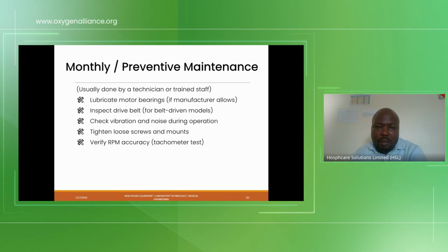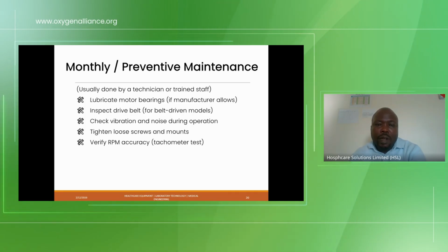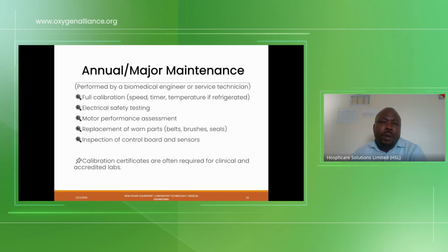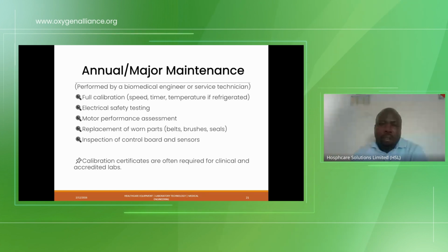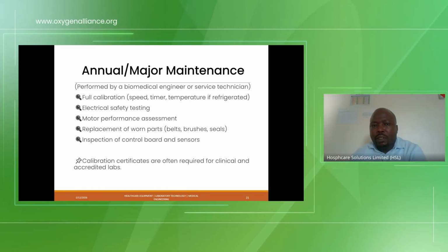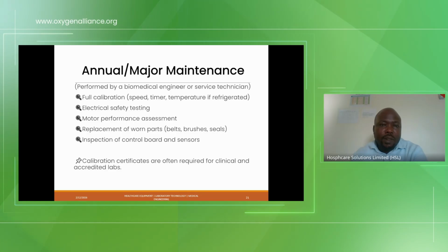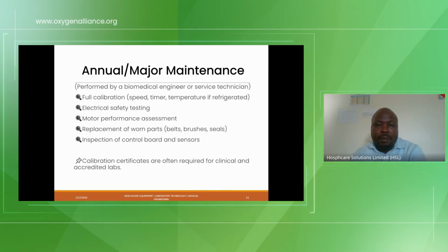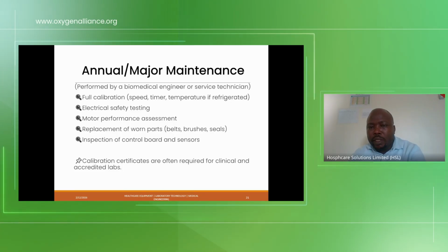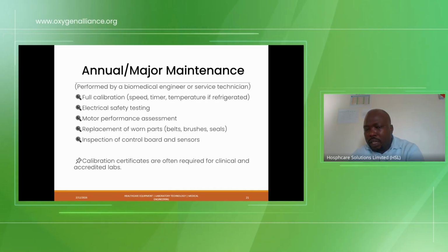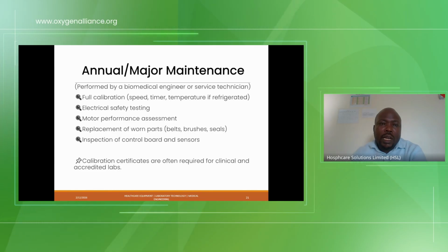You check whether any shock absorbers are broken. You tighten loose screws and mounts. You verify revolutions per minute accuracy using a tachometer test. Annual major maintenance is performed by a biomedical engineer or service technician. You need to fully calibrate. What do you calibrate? Speed, time, and temperature. If it's a refrigerated case, you also check electrical safety testing, motor performance assessment, replacement of worn out parts such as belts, brushes, and seals, and inspection of the control board and sensors. A calibration certificate needs to be issued upon conducting this procedure.